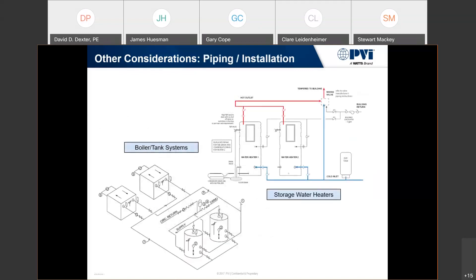From a simplistic point of view, a water heater goes through the same testing standards for certification. The difference is it's a system — we have stored water inside that same appliance that's judged to that efficiency. We're not changing anything when it comes to the actual system with regards to the true efficiencies the owner will see. You'll notice where the building recirculation loop comes back — we're not tying it into the cold water feed to the heaters; we're tying it into the mid-body of the storage tank.